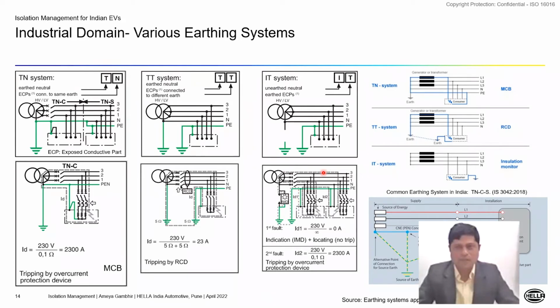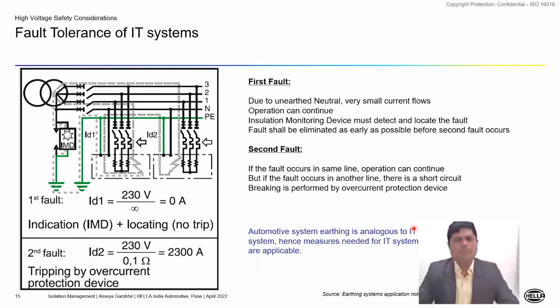So this slide also gives a picture about what is the common earthing system in India. So in India, as per the IS 3042 standard, we are following the TN-C-S standard. So basically this system. So now let's have a look at the fault tolerance of the IT system, because this is an important part for IMD. So the beauty of the IT system is that the availability of power is ensured at the maximum.